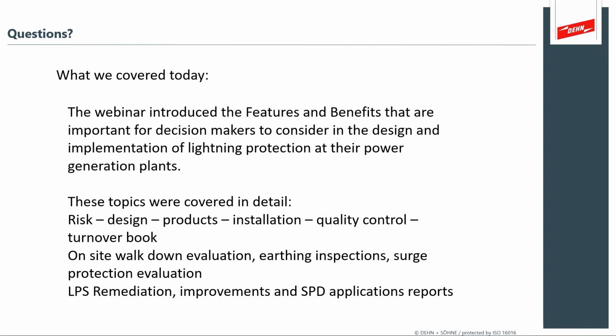Then, okay. Clamp-on and other low frequency meters cannot measure impedance. Why? They are measuring resistance. Why do you infer they are providing impedance values? The clamp-on meters measure resistance. That's correct. Yes. And the inference is that it's a low impedance connection to the soil.